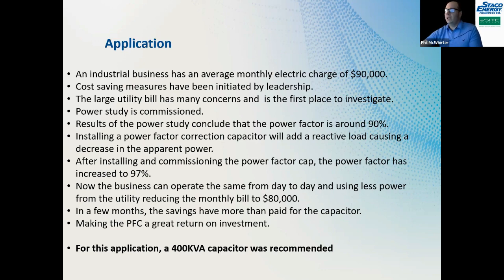Let's figure out what's going on in our facility. So let's do a power study to measure all of the loads on all the motors and see what's going on. After the power study was completed, we concluded that the power factor is around 90%, and anything below 95 is probably going to fall into that poor power factor range. So we recommended installing a power factor correction capacitor to add some reactive load, a capacitive load, to decrease the apparent power. This will minimize that gap in the waveforms from the previous slide. It minimizes the foam in your beer.